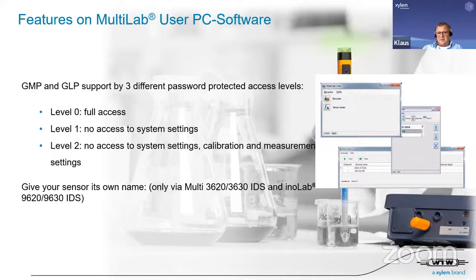That means there's no access to system settings, particularly date and time, which is very critical and should not be altered by people who are not allowed, who have no access to this. It's strictly forbidden to change the date and time in such GLP surroundings. And level 2 means that you have no access to system settings, also no access to calibration or measurement features. So the only thing is measuring and storing, no other possibilities. And what's also nice, if desired, with the big meters we can also name these IDS sensors so that we can give them a different name if desired.